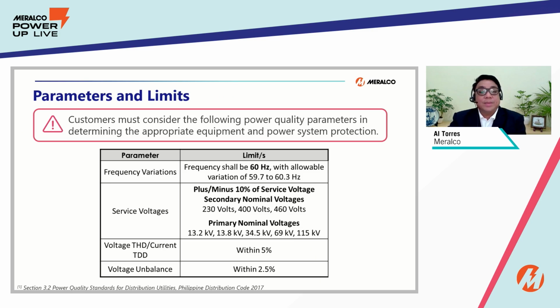So let me share with you the parameters and limits based on the Philippine Distribution Code. The first parameter is the frequency. Frequency shall be 60 Hertz with the allowable variation of 59.7 to 60.3 Hertz. Next parameter is the service voltage. The allowable limit is plus minus 10% of the service voltage, either for the secondary voltage customers or primary metered customers. Next parameter is the voltage total harmonic distortion and current total demand distortion. Based on the Philippine Distribution Code, the limit is 5%. While lastly, the voltage unbalance, and the limit is 2.5%.